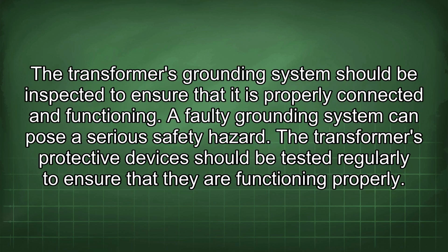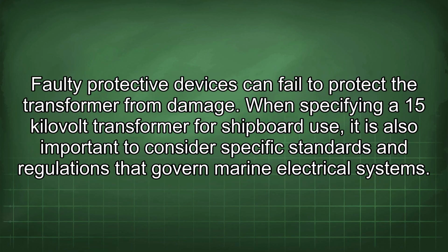The transformer's grounding system should be inspected to ensure that it is properly connected and functioning. A faulty grounding system can pose a serious safety hazard. The transformer's protective devices should be tested regularly to ensure that they are functioning properly. Faulty protective devices can fail to protect the transformer from damage.